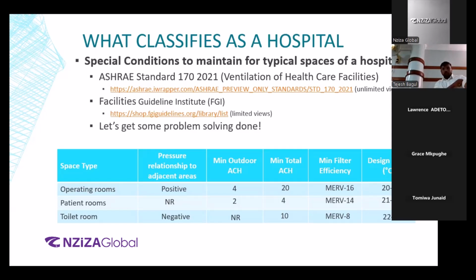Right. Now, talking about design temperature, as I mentioned, all of our spaces will need to be maintained at given environmental conditions. If it is too high, we run into the risk of the patient sweating more, getting exhausted more, getting dehydrated more. On the other hand, if it is too cold, the heat loss from that patient's body will be much larger. And as I said, patients are very scantily clad in a given hospital area. So we need to make sure that the temperatures are also met over here. Okay. Does that make sense till now? What we are looking for?